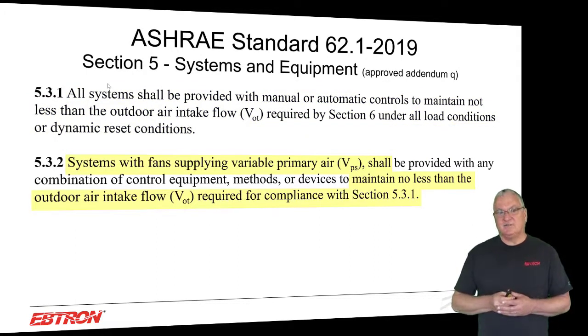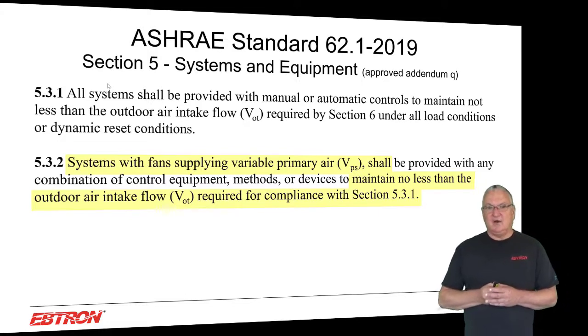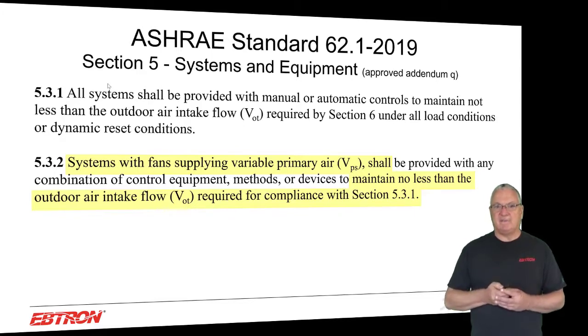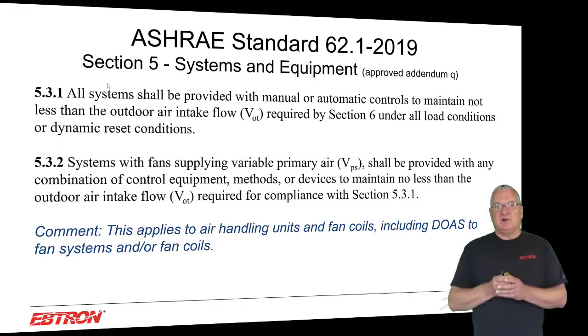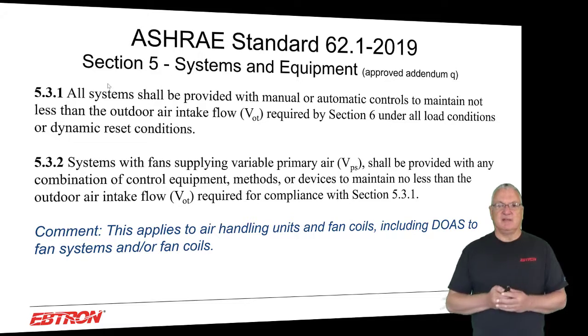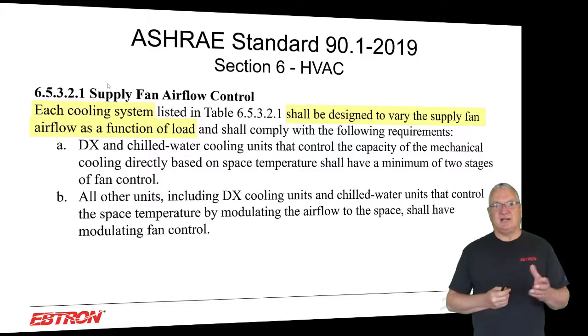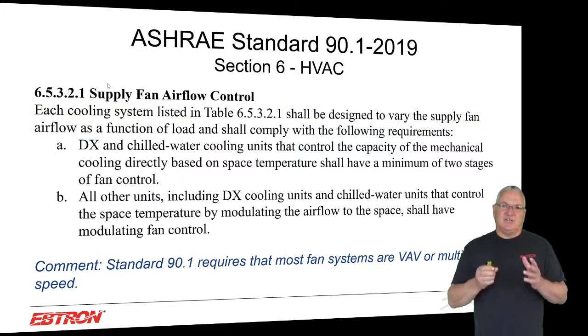Systems with fans supplying variable primary air — such as variable-speed fan coils — shall maintain no less than the outdoor air intake flow required for compliance with section 5.3.1. The scope of where you need active and dynamic control has become broader than it was several years ago. The reason for that is the requirement under Standard 90.1 that each cooling system shall be designed to vary the supply fan airflow as a function of load — so it's not just VAV anymore.